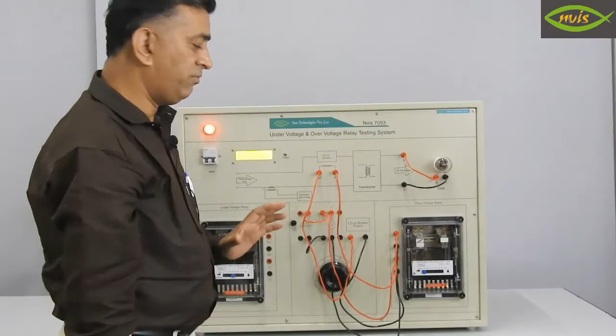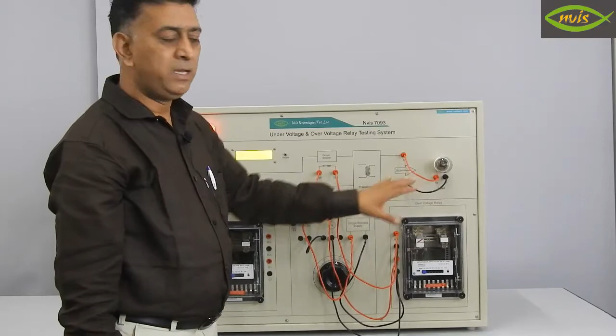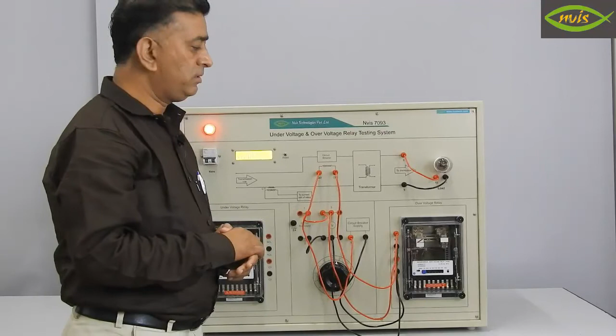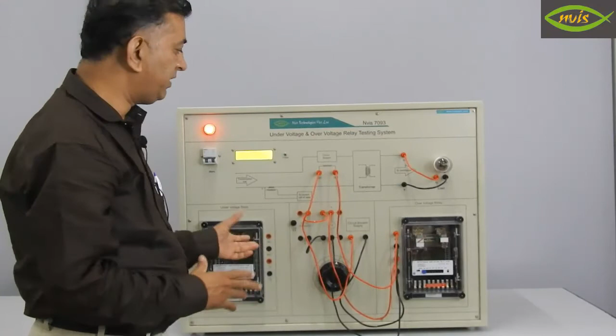As I just crossed 121 volt, the relay is tripped. So it performs well. It did its function. It disconnected and protected the load. This is the objective of the over voltage relay. In any distribution line, whenever the voltage increases, the connection of the transmission line should be switched off. So this is about the over voltage relay, and today we saw the under voltage and over voltage relays, how they function, what different power supplies are required, what the plug settings are, and how the load is provided with safety with the help of these relays. Thank you.